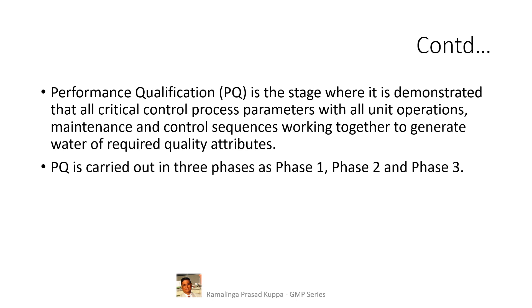Then, continue with phase 2 validation. In phase 2 validation, a reduced number of sampling points may be considered, and the selection of sampling points should be justified through a risk assessment report. It is recommended to make reports for phase 1 data and phase 2 data to establish that the system is set for full validation. If there are any modifications required, it may be justified to continue the validation program for longer periods.